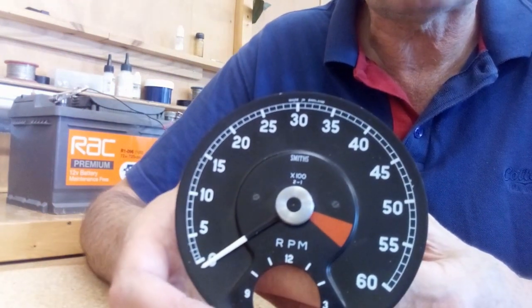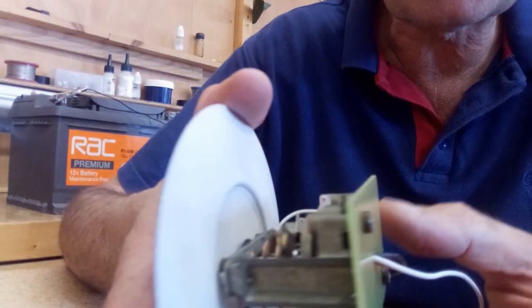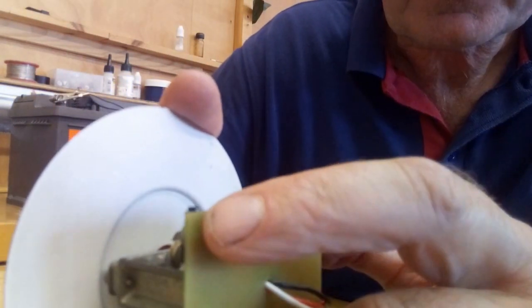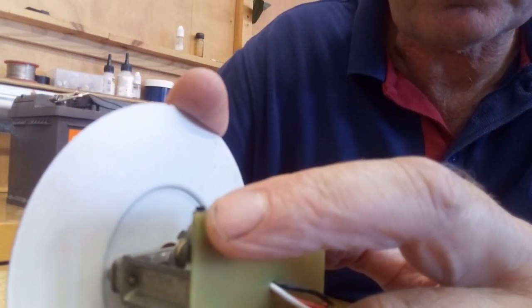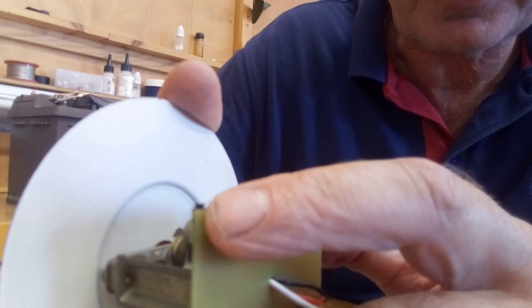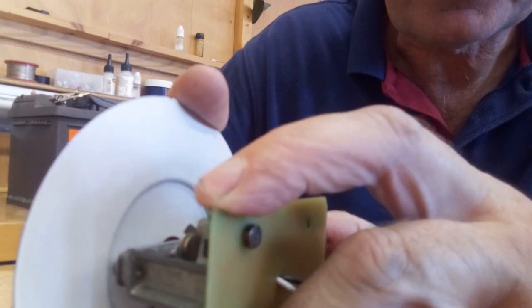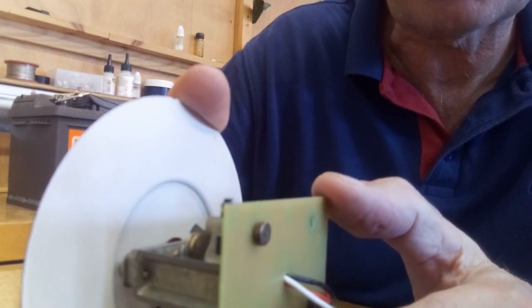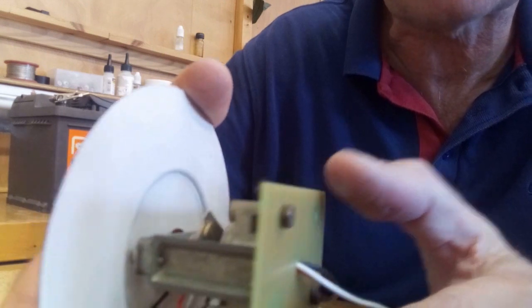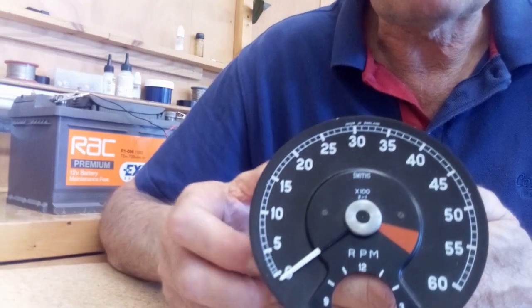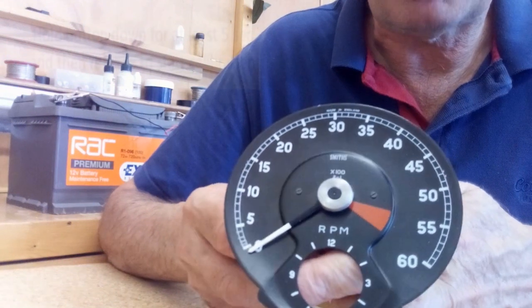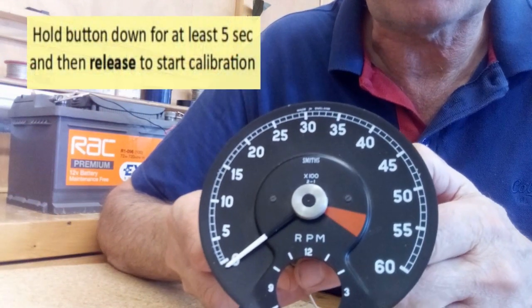The calibration is carried out using this calibration button on one corner of the circuit board. It's quite small, but if I press it, it gives an audible click so you can easily tell when it's been pressed. To start the calibration, you hold the button down for 5 seconds, which I'm going to do now.